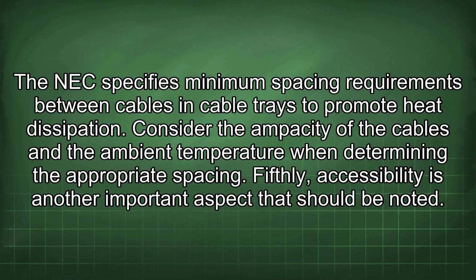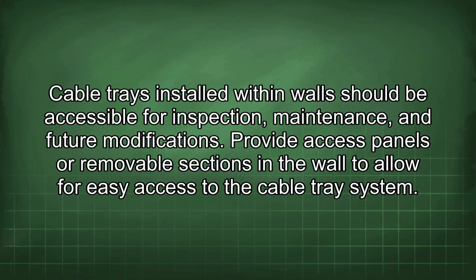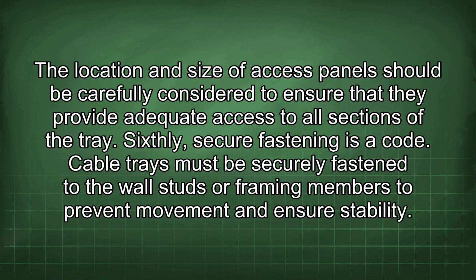Fifthly, accessibility is another important aspect that should be noted. Cable trays installed within walls should be accessible for inspection, maintenance, and future modifications. Provide access panels or removable sections in the wall to allow for easy access to the cable tray system. The location and size of access panels should be carefully considered to ensure that they provide adequate access to all sections of the tray.